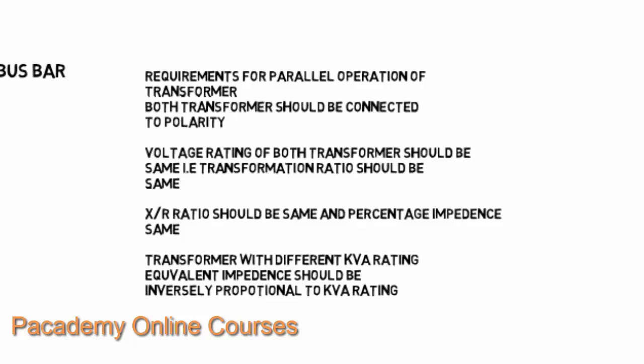The reactance-to-resistance ratio should be the same, and the percentage impedance should also be the same for both transformers. If both transformers are of different KVA ratings — for example, one is 100 KVA and the other is 50 KVA — then the equivalent impedance of each transformer should be inversely proportional to their KVA ratings.